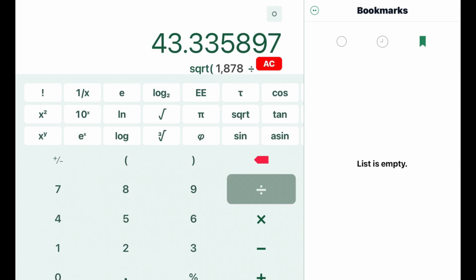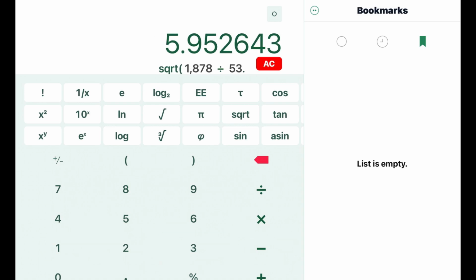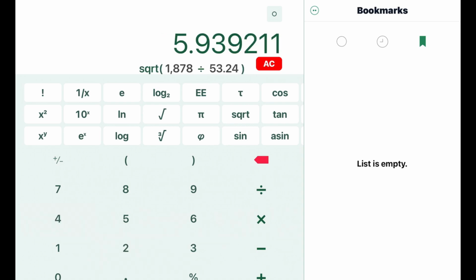We had 1878 ohms. We'll divide that by our reading across the primary with the high voltage winding shorted, 53.24, and that gives us a turns ratio of 5.94.